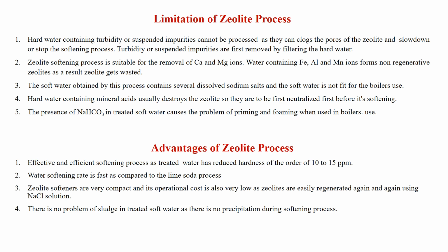There are advantages of zeolite process. The common advantages are this process is effective and efficient, as the treated water has reduced hardness of the order of 10 to 15 ppm. Water softening rate is fast as compared to lime soda process.